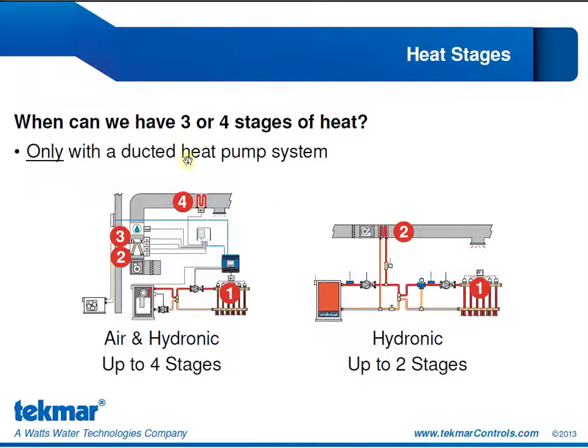So an example where we have 4 stages of heat is shown on the left-hand side, where we have radiant floor as first stage heat, a heat pump providing a second and third stage of heat, and an electric strip backup providing a fourth stage of heat. If you look at the example on the right, it is strictly a hydronic system, and only two stages of heat are possible, the radiant floor and the fan coil. We cannot control an electric strip backup in this situation with the 557.